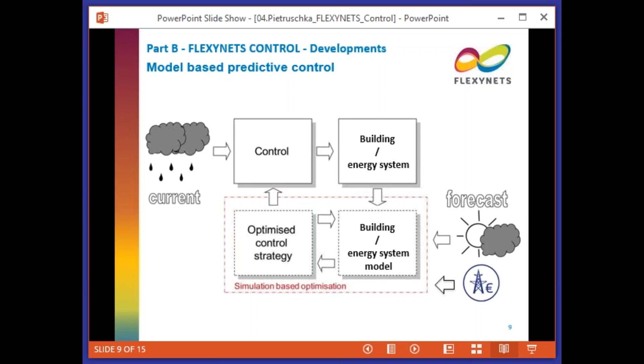So how are we operating on the installation side, or the controller side? As I mentioned, we have substation controllers in each station, which can also cover sub-device controllers for the single devices within each substation. This controller is the master of these sub-devices at the station level, responsible for operating the systems in an optimized manner. It's connected to a web interface where you can access the controller, see what happens, and change schedules, and it's also connected to the higher-level control.